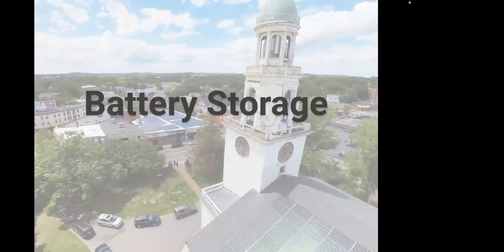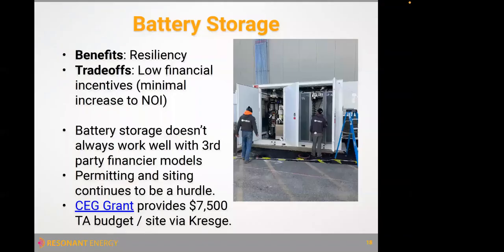One additional item that we wanted to introduce here is to talk through battery storage. So one question we get a lot is, solar's great, but when the power goes out, the solar turns off, and so we are not achieving a resiliency benefit. So in terms of batteries, this is an example of a commercial size battery installation that we completed recently. The benefits, of course, are resiliency, which is as long as your battery is installed with an automatic transfer switch, when the power goes out, that switch gets tripped, similar to the type of ATS switch that you would see with a generator. And your building is able to continue operating on a more limited basis with the battery that has been fully charged by your solar.